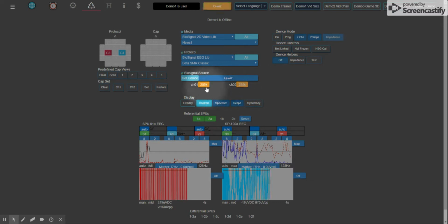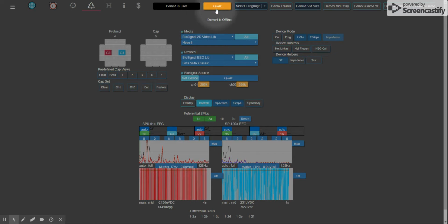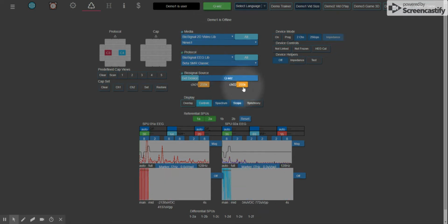And there it goes. It goes up to its maximum value because it's not connected. It's orange. It's flashing here to say we've got an issue. And it's showing its maximum impedance value of 255. To be a good signal, it should be less than 50 for both electrodes here. Now, this particular protocol we've chosen is a 2-channel protocol, and that's why it's showing channel 1 and channel 2. Had it been a 4-channel protocol, then we would have had the 4 sites represented down here, or had it been a 1-channel protocol, then there'd be just the 1 electrode shown here.